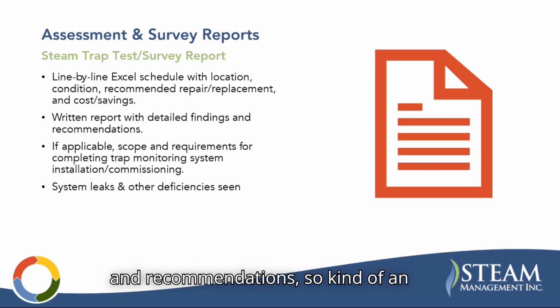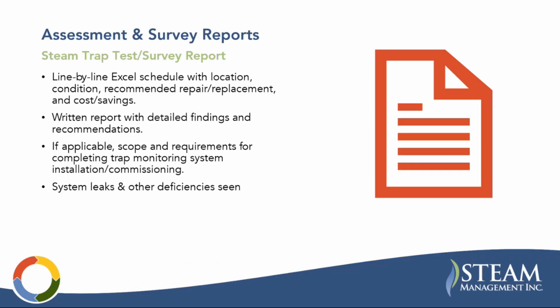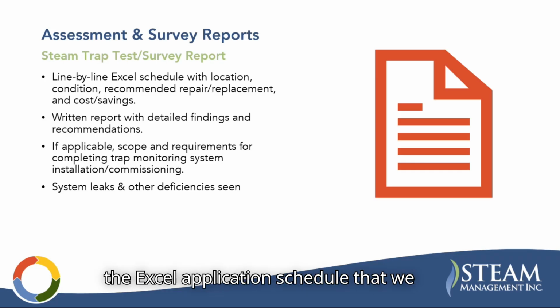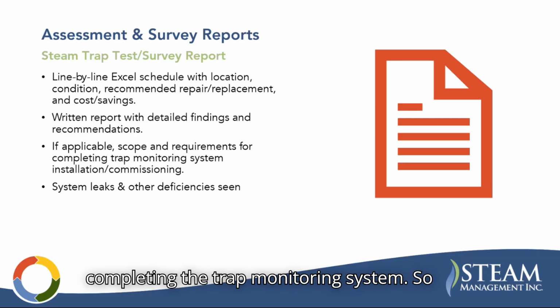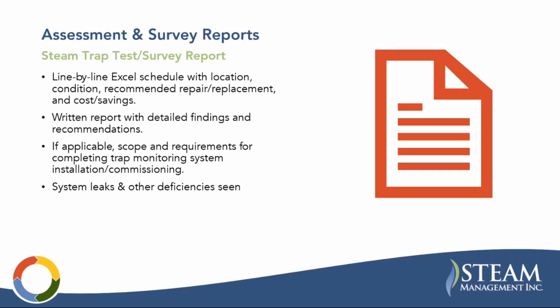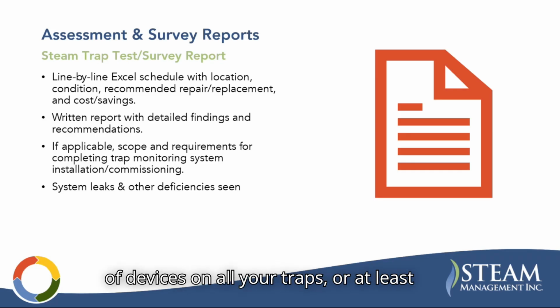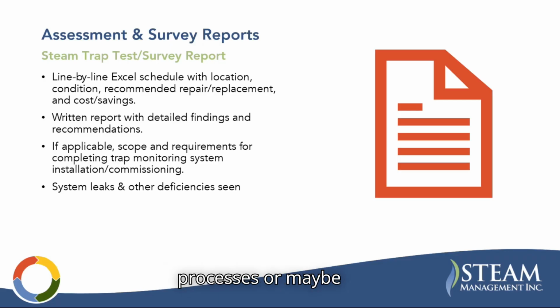A written report with the detailed findings and recommendations, an associated write-up to describe what we're seeing and support the Excel schedule that we provide. And then, if applicable, scope and requirements for completing the trap monitoring system. A trap monitoring system is a device on a trap, or a whole population of devices on all your traps, or at least your priority traps, that will monitor those traps and let you know if they fail. There are different types of technology to do that, but it can really make sense if you have high fuel costs, high run hours, critical processes, or constrained manpower on your maintenance team, right? Like the facility is not able to get around and test and maintain the traps. Then you can put a monitor on it and let that monitor do it for you.